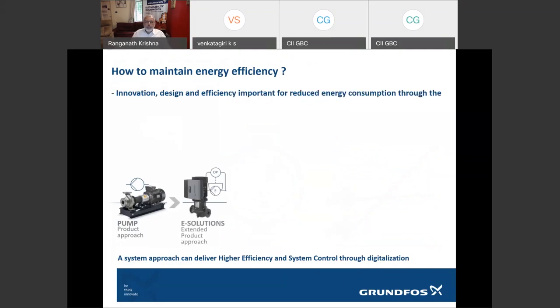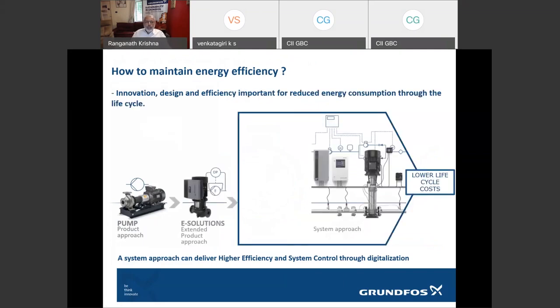You can be very efficient, you can choose the most efficient pumps. How do you maintain energy efficiency over the life cycle? Basically, it requires innovation, design, and efficient equipment to ensure that we have reduced energy consumption through the life cycle of the pump. Now, if you look at pumps, earlier we had pumps which were fixed speed. Then we started getting pumps with variable speeds with a drive algorithm. Now you have pumps with the drive on the motor itself with all the sensors built in.